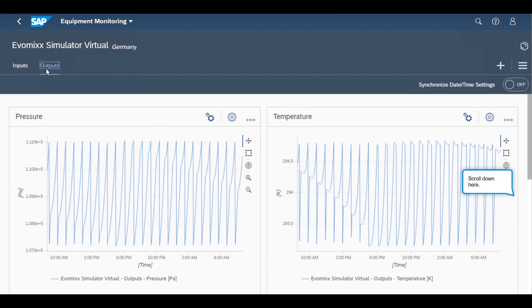In the Output tab, the systems engineer can view output calculated data for the valve — that is, temperature and pressure values in the tank calculated by the Modelica model. This means that operators can monitor physical parameters such as pressure and temperature values in real time without needing to place actual sensors. It is also possible to define threshold values to get alerts on these parameters.